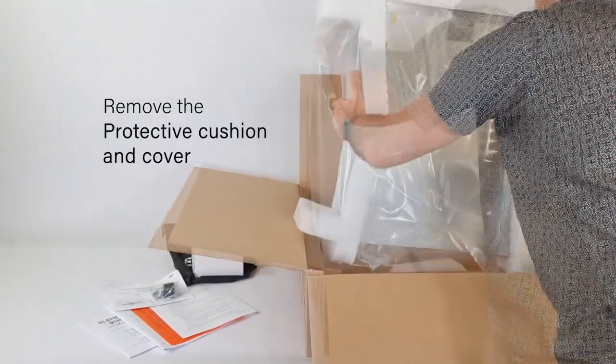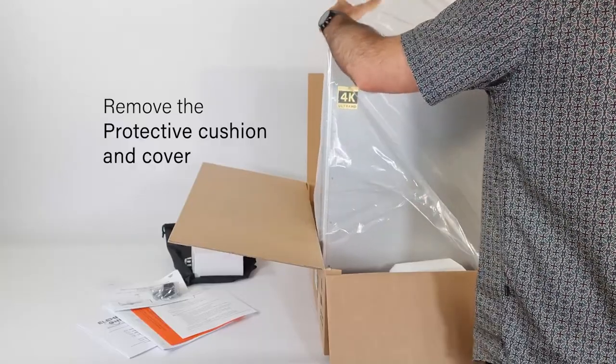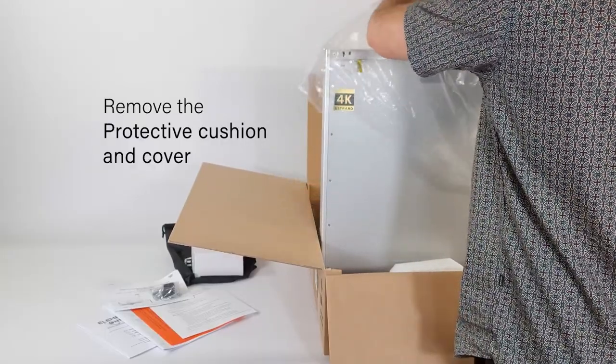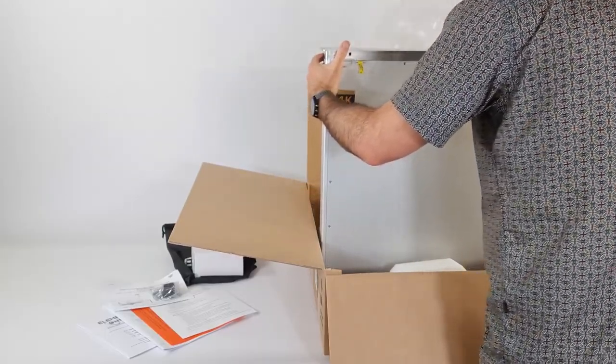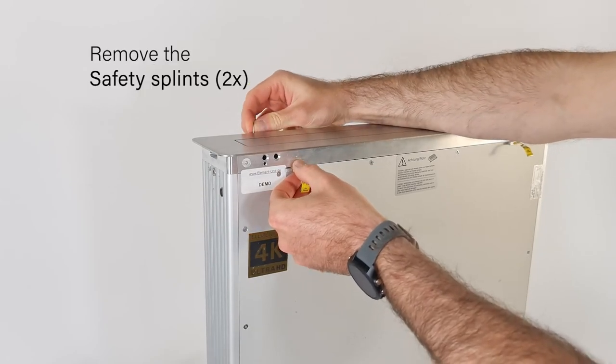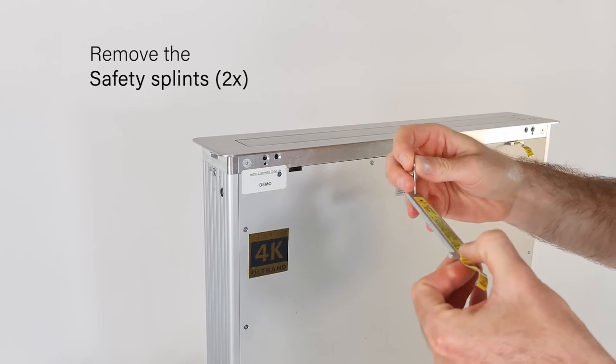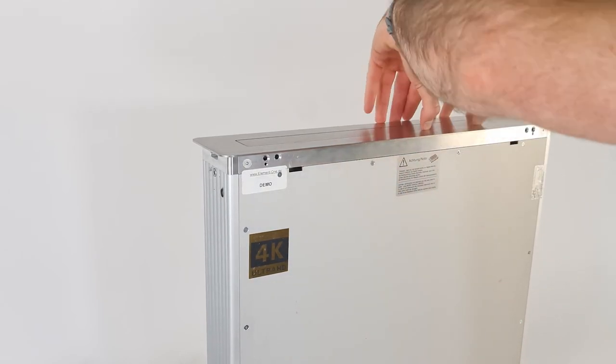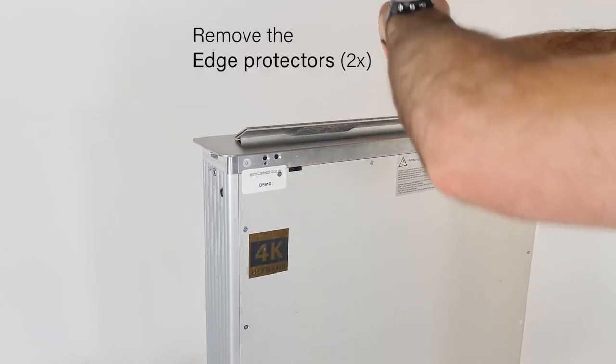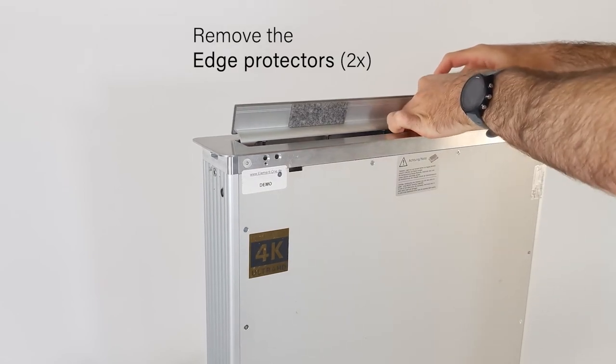Now you can start to remove the protective cushion and the cover. The monitor is secured for transport with two safety splints on the upper side of the device. Please remove these. Open the cover flap carefully and then remove the two edge protection caps.